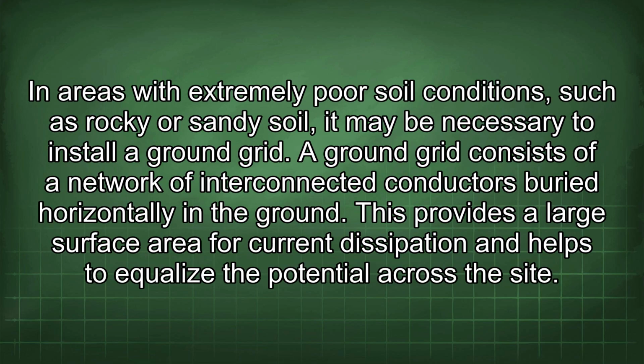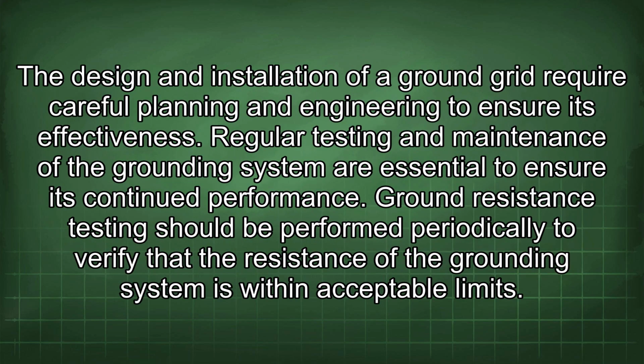In areas with extremely poor soil conditions, such as rocky or sandy soil, it may be necessary to install a ground grid. A ground grid consists of a network of interconnected conductors buried horizontally in the ground. This provides a large surface area for current dissipation and helps to equalize the potential across the site. The design and installation of a ground grid require careful planning and engineering to ensure its effectiveness. Regular testing and maintenance of the grounding system are essential to ensure its continued performance.